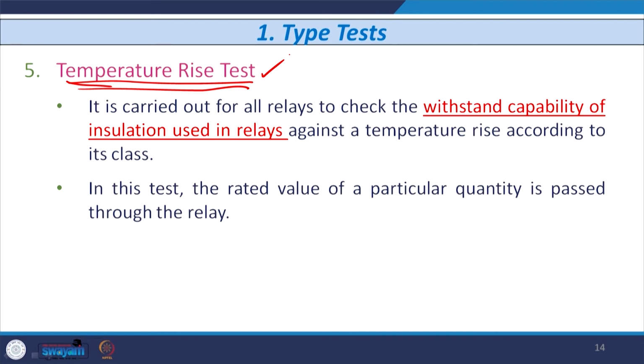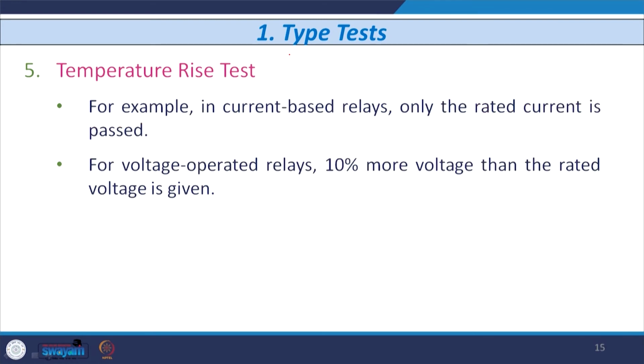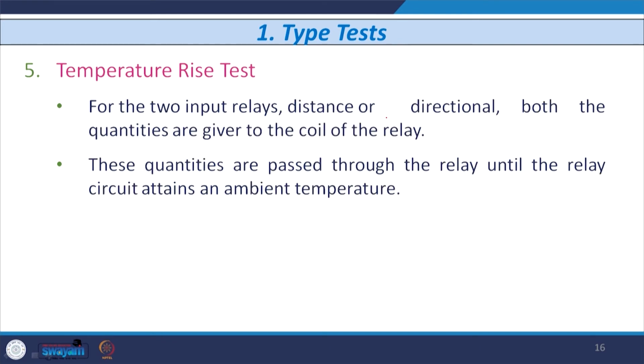In this test, the rated value of current or quantity is passed through the relay, and then the temperature is noted down. For example, in case of an overcurrent relay, the rated current is passed through the relay, and in case of a voltage-based relay, 10% higher than the nominal value is given, and the temperature rise is noted. For a two-input relay like distance and directional, both current and voltage quantities are given to the respective current coil and voltage coil of the relay, and these quantities are passed through the relay until the relay circuit attains the ambient temperature. So, this test is related to the temperature rise because of the quantity passing through the coil of the relay.